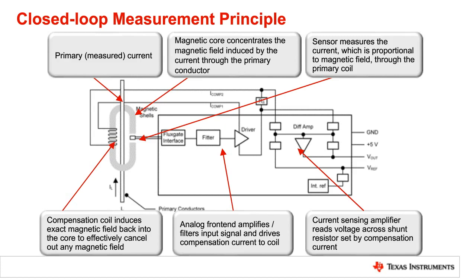So what we're essentially looking at is how much current is required to drive that magnetic field to zero, using the flux gate sensor as our reference point. We have an analog front end that measures the amount of current through that coil and gives us the output. So we're not directly measuring the sensor, but measuring how much current is required to bring that back to zero.